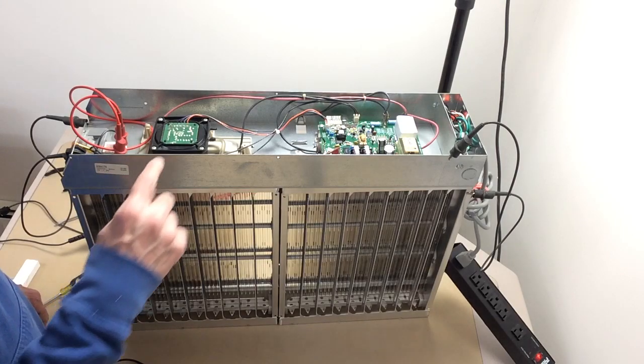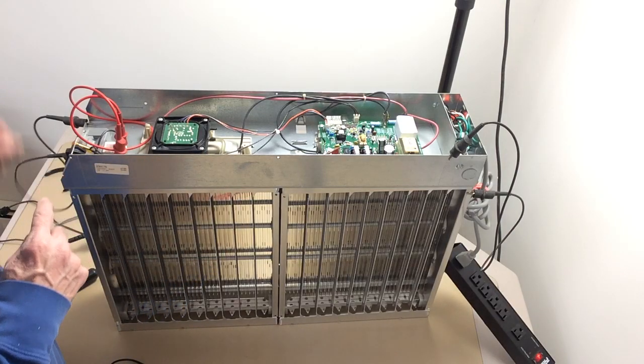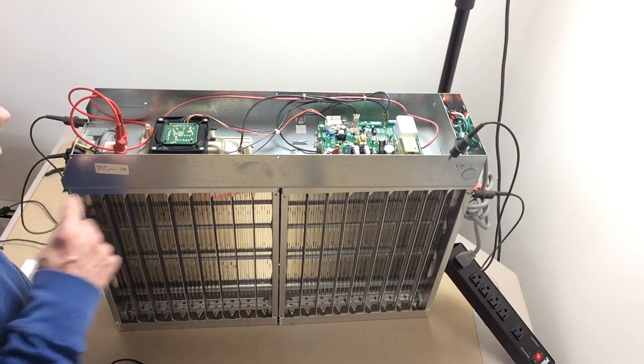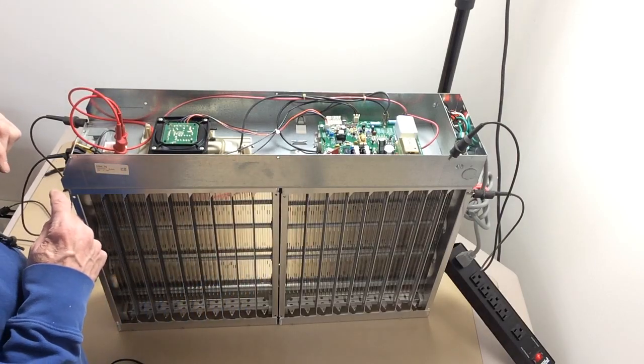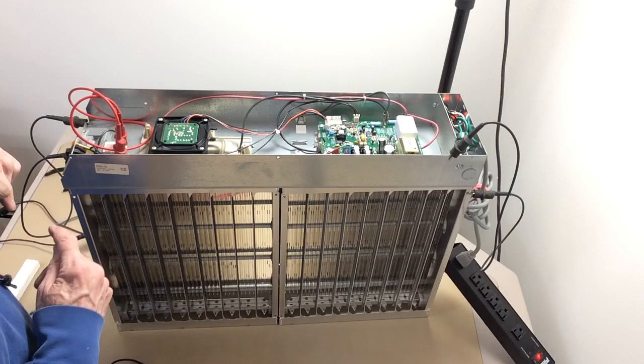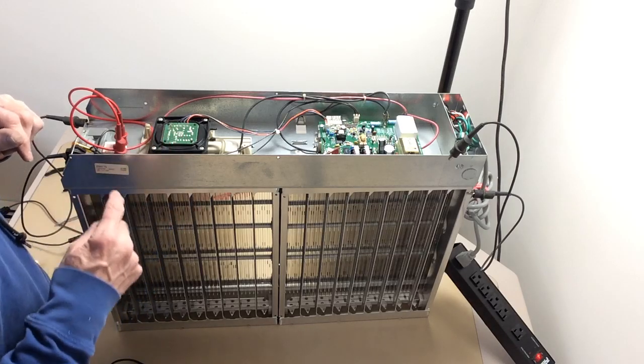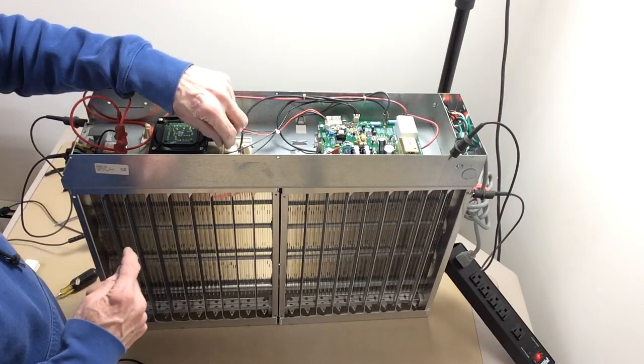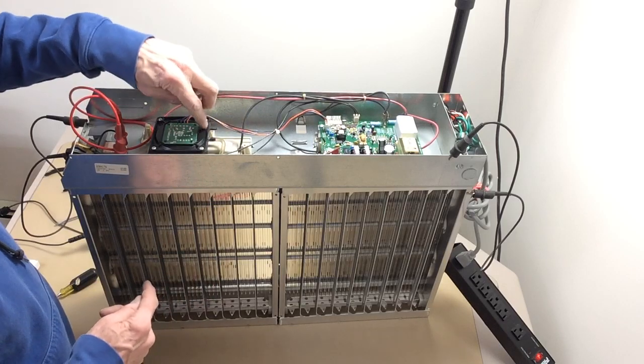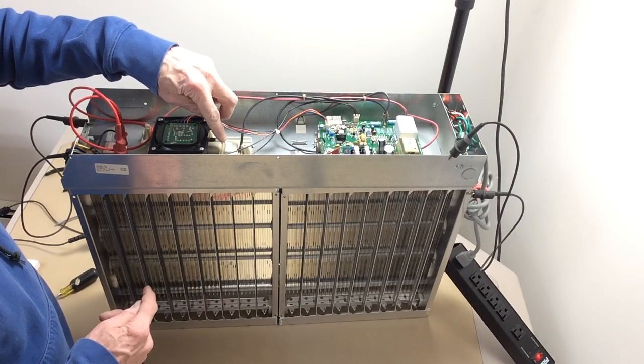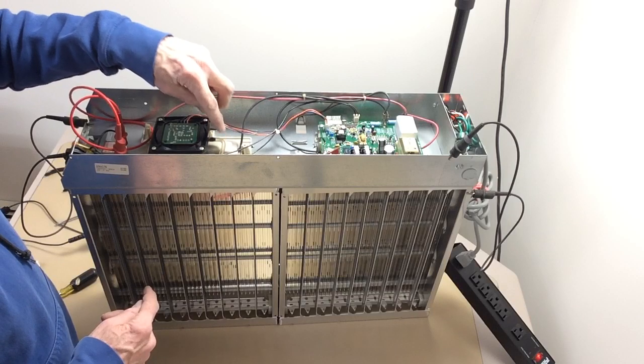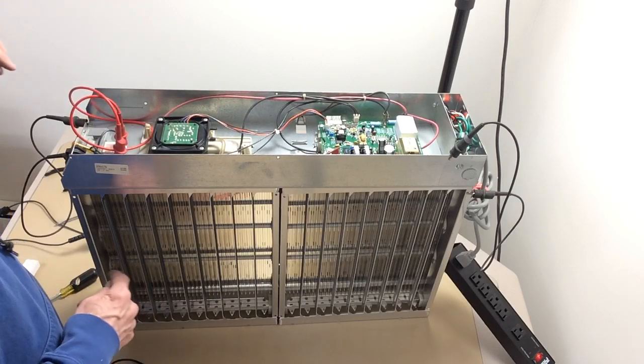Today I'm going to show you a test procedure we use to bypass the airflow sensor. These electronic air cleaners won't power up unless it senses airflow in the ductwork, and it does that by sensing a vacuum. That's what this device does. This side of the nozzle senses a vacuum and this nozzle senses pressure.